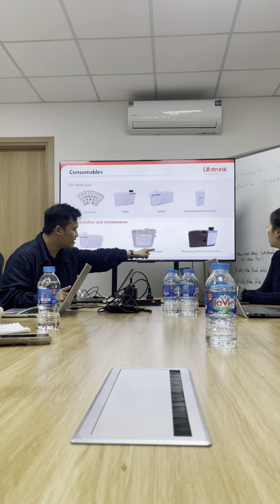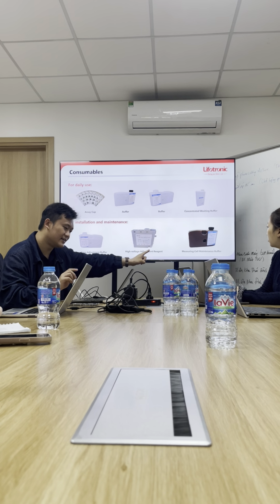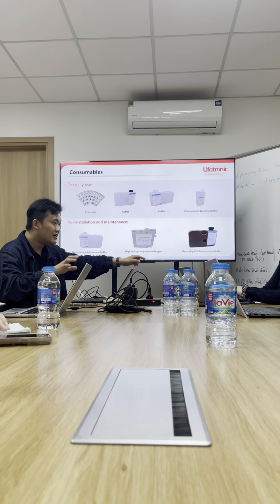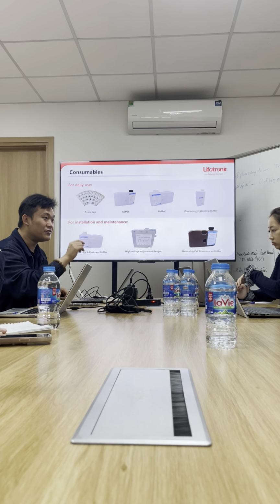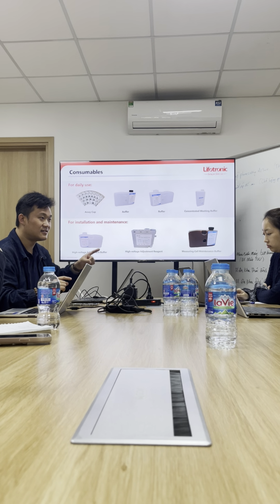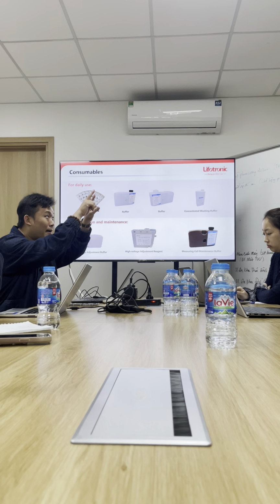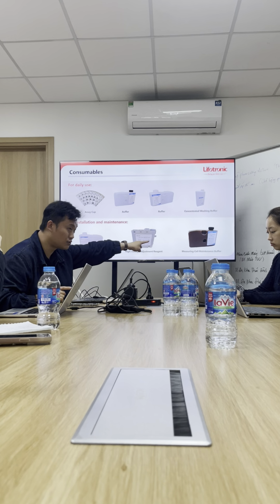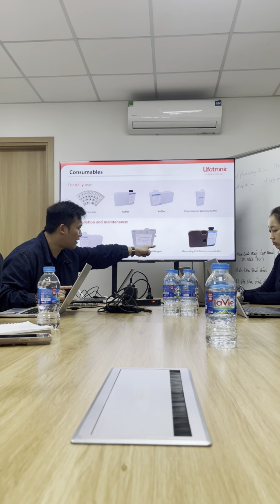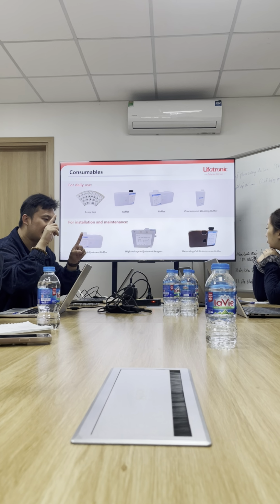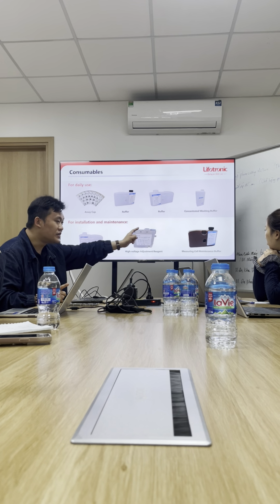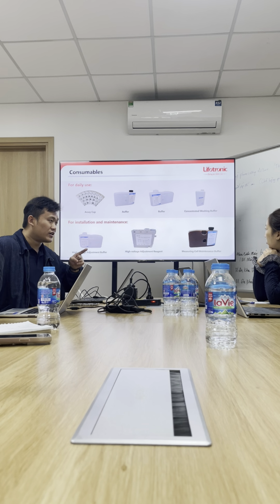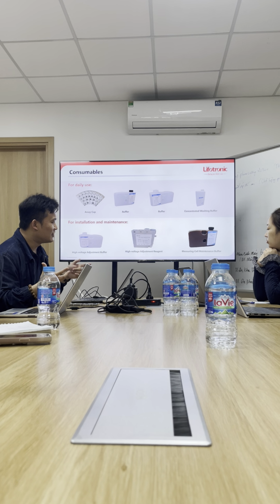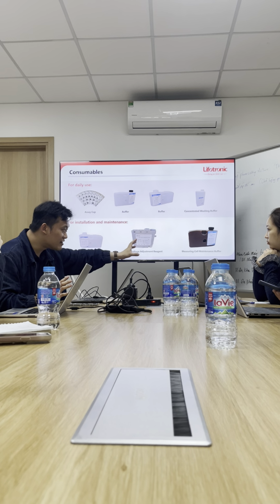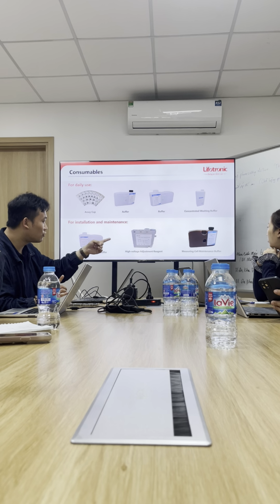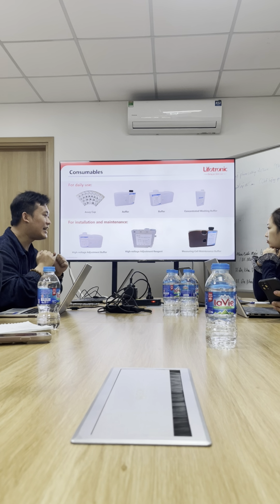The end user uses the measuring cell maintenance buffer every 2 weeks or every 2,000 tests. The machine will give a reminder if you do not do the measuring cell maintenance after 2 weeks or after 2,000 tests. It will give a warning, and the doctor can use this to do the measuring cell maintenance. This buffer can do an average of 100 tests, which means for one machine, on average consumption, it can normally be used for nearly half a year, one bottle for one unit, depending on your reagent consumption.